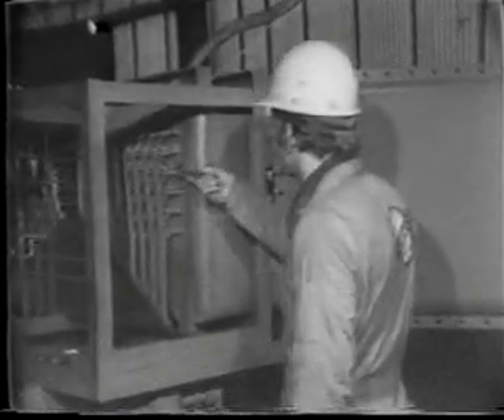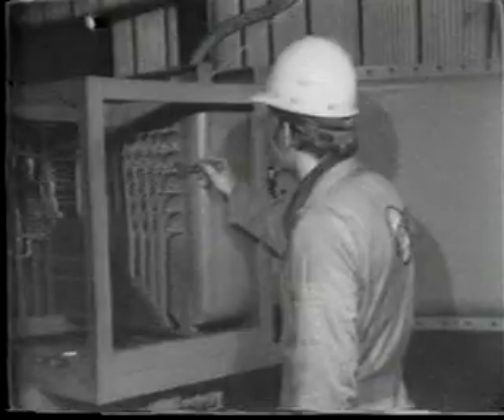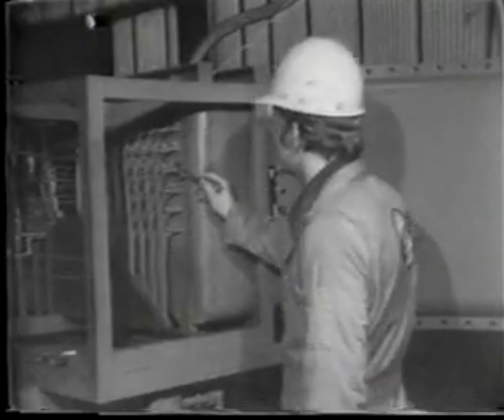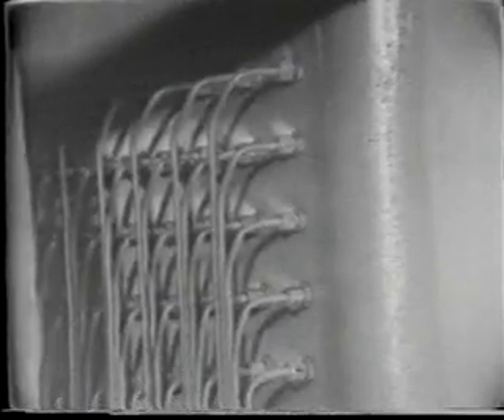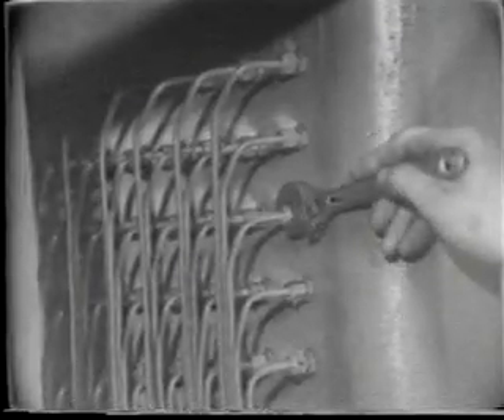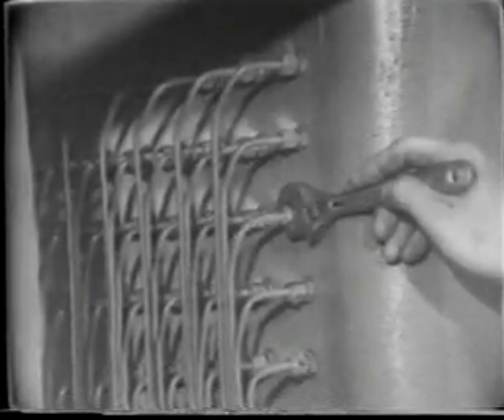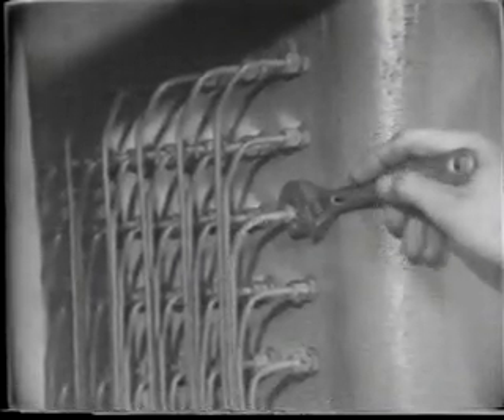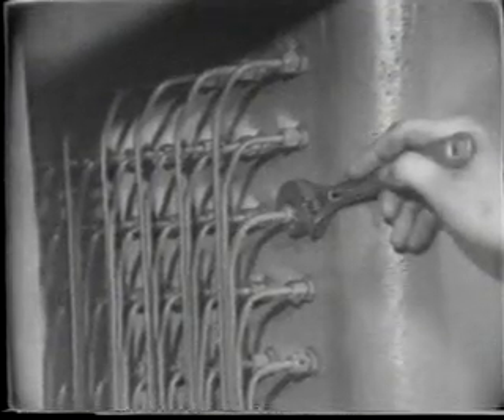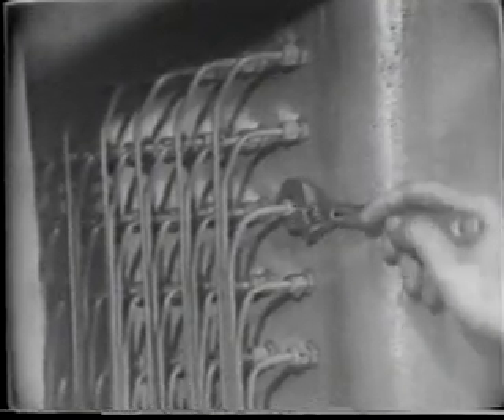If no voltage is present across the terminals in the manifold, then check the pressure switch for that function. This is done by checking the schematic to find the correct pressure switch and then partially loosening the fitting at the back of the explosion-proof junction box to see if there is pressure in the line leading to the pressure switch. If there is pressure in the line, then check all of the wiring for a loose connection or a short.